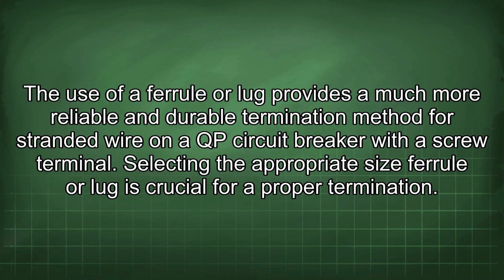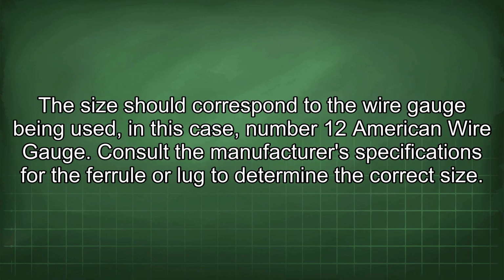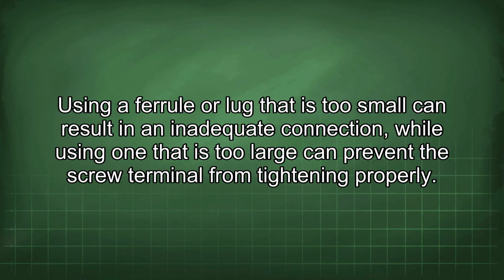Selecting the appropriate size ferrule or lug is crucial for a proper termination. The size should correspond to the wire gauge being used, in this case, number 12 American wire gauge. Consult the manufacturer's specifications for the ferrule or lug to determine the correct size. Using a ferrule or lug that is too small can result in an inadequate connection, while using one that is too large can prevent the screw terminal from tightening properly.